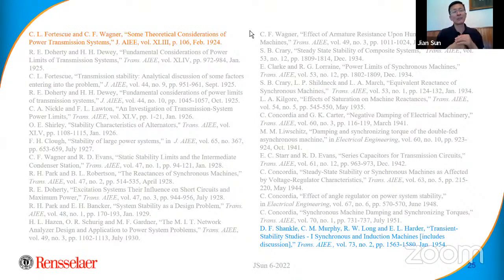The last point I want to add is that even the harmonic, because of the history of this nonlinear behavior and distortion, when these resonances start to appear, the first reaction people had was 'that's a power quality problem.' Well, it's actually not, it's instability or the beginning of instability. That problem is going to get worse, because the fundamental issue is these converters have control, and the control creates negative damping. If you measure the impedance in the harmonic frequency range, the impedance has a negative real part.